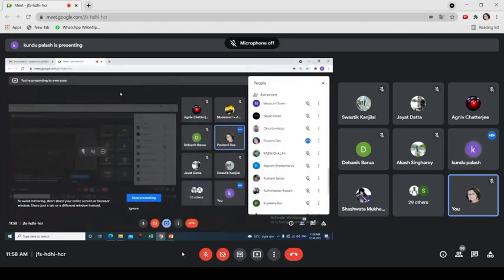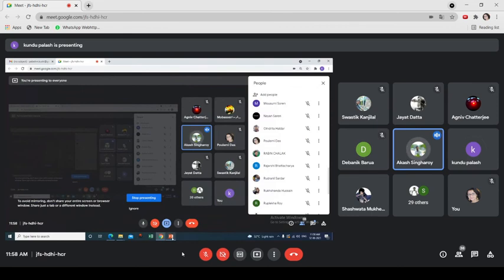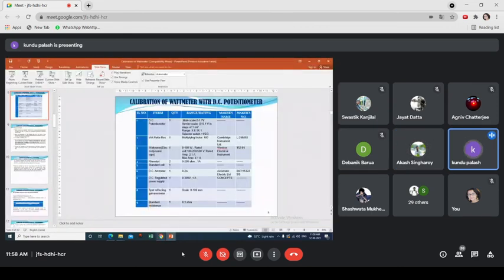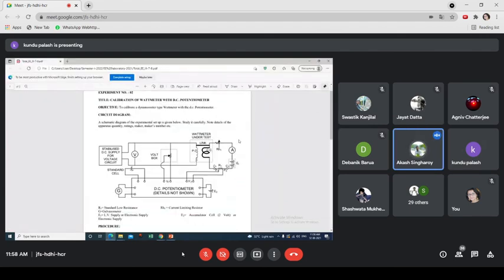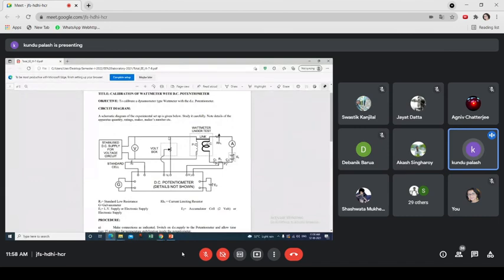Okay, sir. Sir, in the circuit diagram, can you tell us the function of the volt box? Which one? The volt box, V1. As mentioned in the videography, the rated voltage of the potential coil is fixed at 100 volt, adjusted to 100 volt from the DC supply. But the potentiometer cannot accept the 100 volt high voltage. The potentiometer can handle the unknown voltage up to a maximum of 2 volt. So that's why there is a need to reduce the voltage. So basically the volt box is a potential divider circuit. Using the multiplying factor 1:100, we'll get 1 volt, which is applied to the potentiometer.